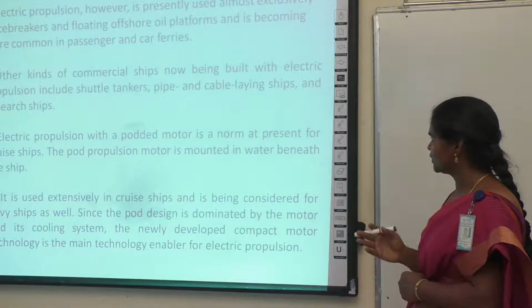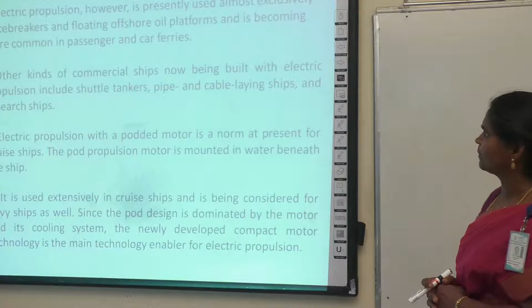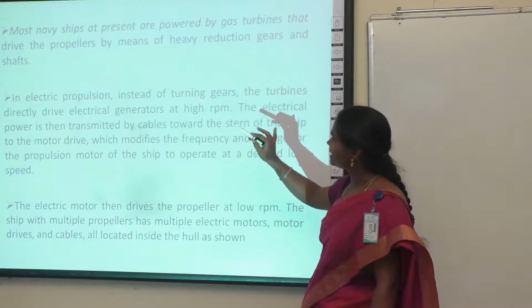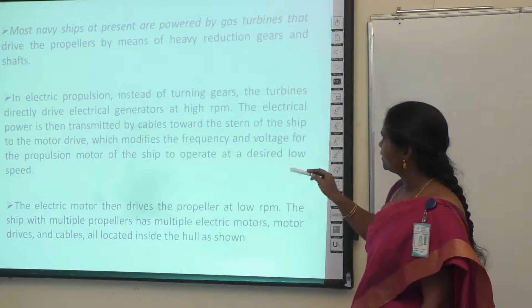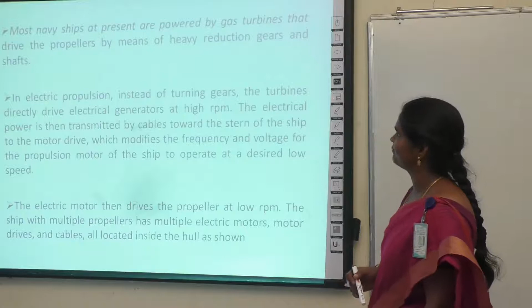Since the pod design is dominated by the motor and its cooling system, the newly developed compact motor technology is the main enabling technology for electric propulsion. Most navy ships at present are powered by gas turbines that drive the propellers by means of heavy reduction gears and shafts. In electric propulsion, instead of turning gears, the turbines directly drive the electrical generators at a high RPM. The electrical power is then transmitted by cables toward the stern of the ship to the motor drive, which modifies the frequency and voltage for the propulsion motor of the ship to operate at a desired low speed. The electric motor then drives the propeller at low RPM. A ship with multiple propellers has multiple electric motors, motor drives and cables, all located inside the hull, as shown in the next figure.